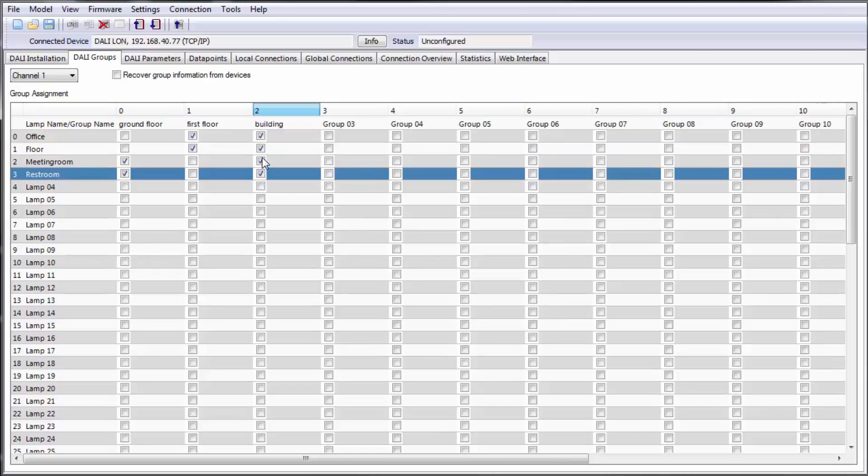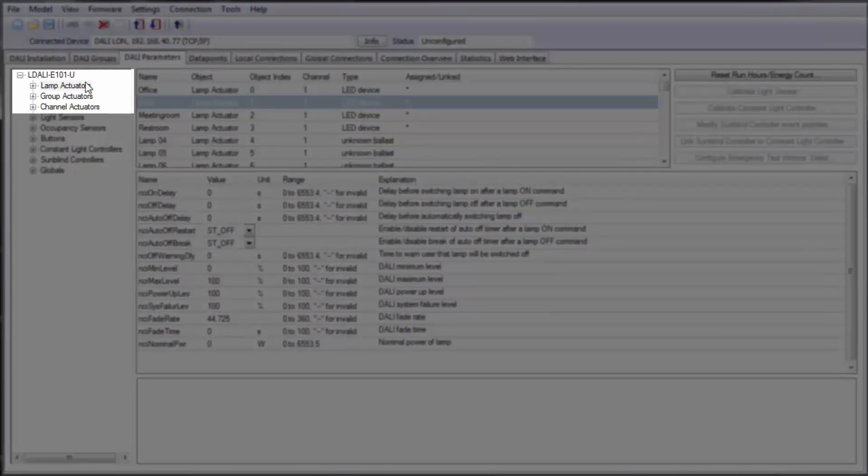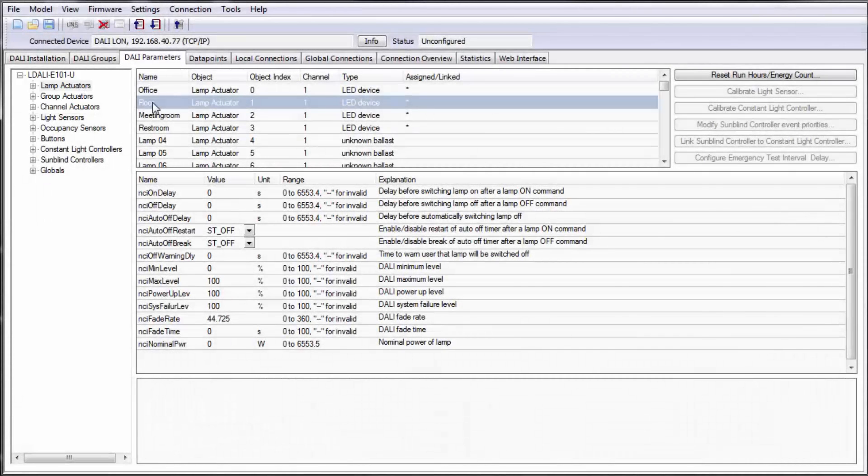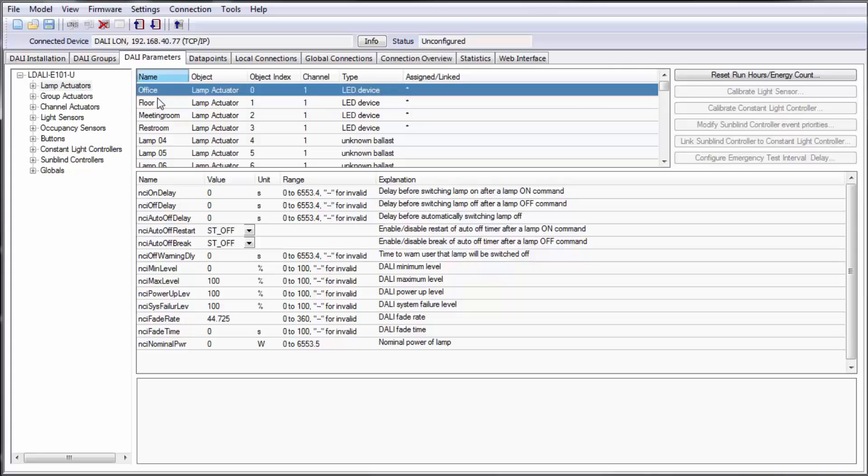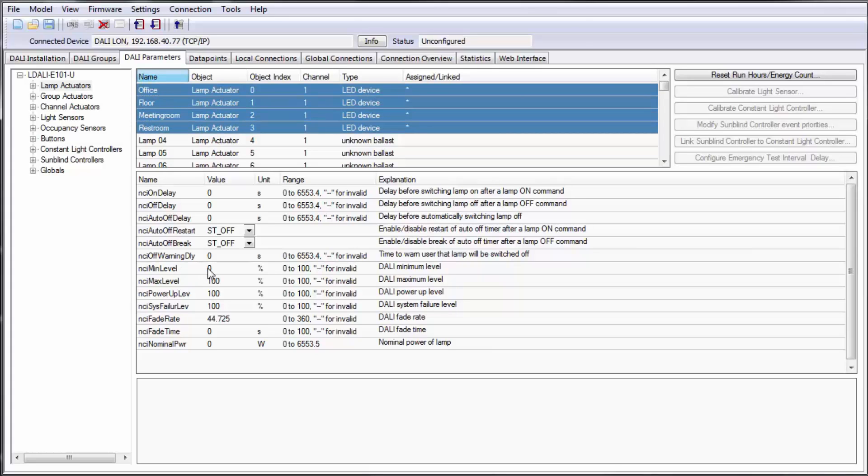In the tab DALI parameters the properties of ballasts, DALI groups and channels can be configured. Amongst other things you can set a minimum level for ballasts, the fade rate, on and off delay and much more. These parameters can be changed for a single device or by using multi-select for more devices at the same time.